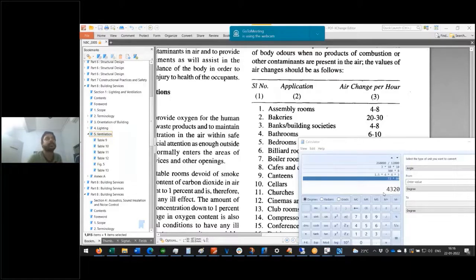Okay, fine. And also the height, I have one question. Discarding the false ceiling, we have to take the height, right? There is a false ceiling in the space. Yes, you could do that, that's a good way. But I would suggest, the higher the room, the lower the temperature. Of course, you can have a lower false ceiling and take the equivalent height, that way your mechanical volume will be less. We can reduce the energy requirement also.